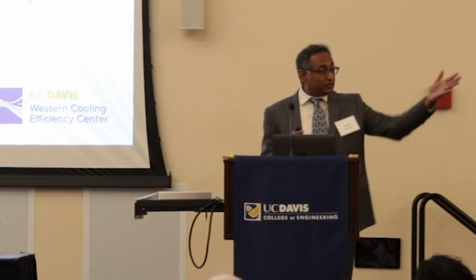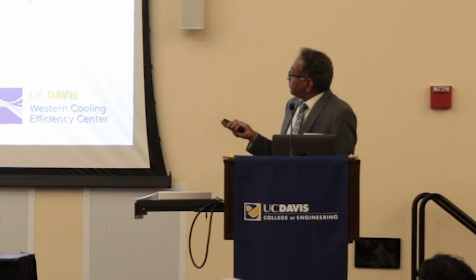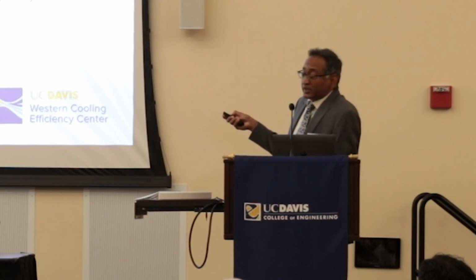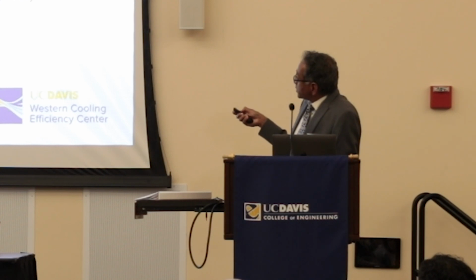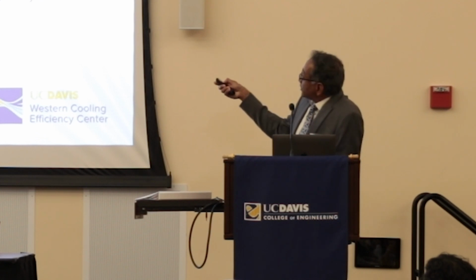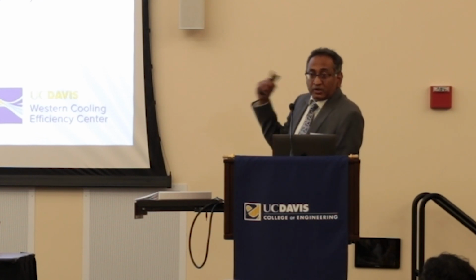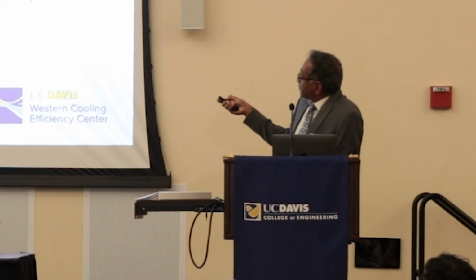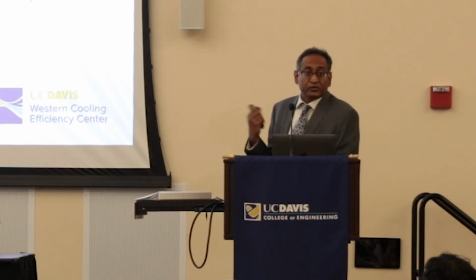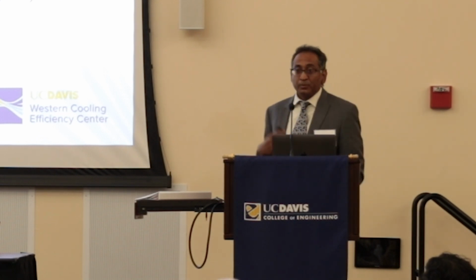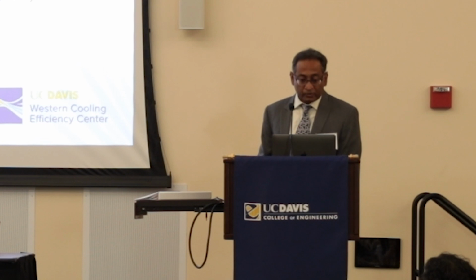And our group, a whole bunch of engineers, are working on this problem. Here is an example of a time series of what happens when you have a multifunctional heat pump in operation in a real house. This is the winter time. So the blue is the outdoor temperature, and this is the indoor temperature, it's maintaining it steady. This is the water tank temperature. So let's say you have a cold winter morning, the defrost cycle kicks on, and instead of using strip heating, it draws heat from the water tank to defrost the outdoor coil, and hence you alleviate the problem of having that extra electrical heating. So that's the multifunctional heat pump. We are working with a bunch of companies to take this technology forward.